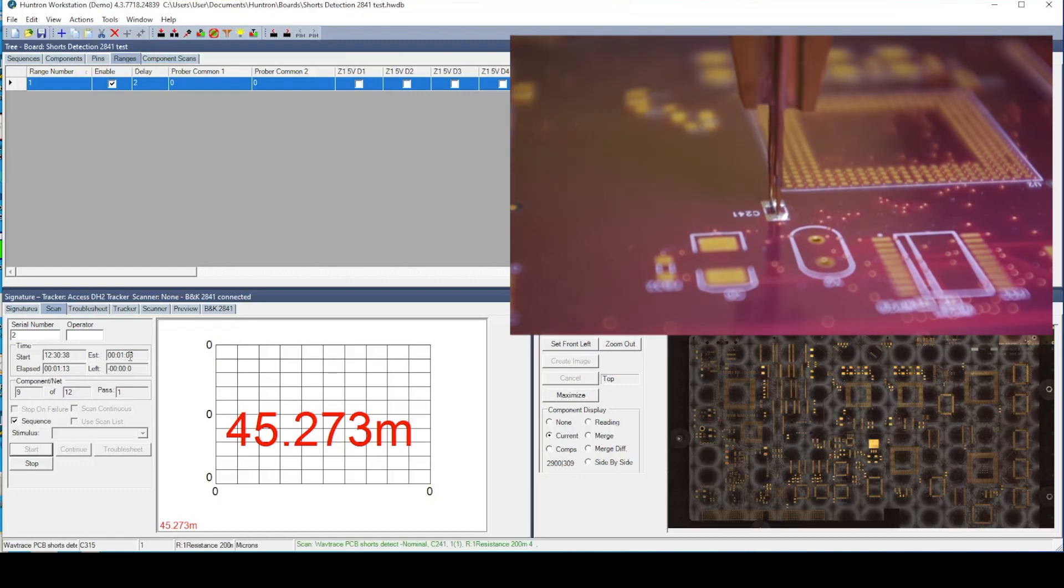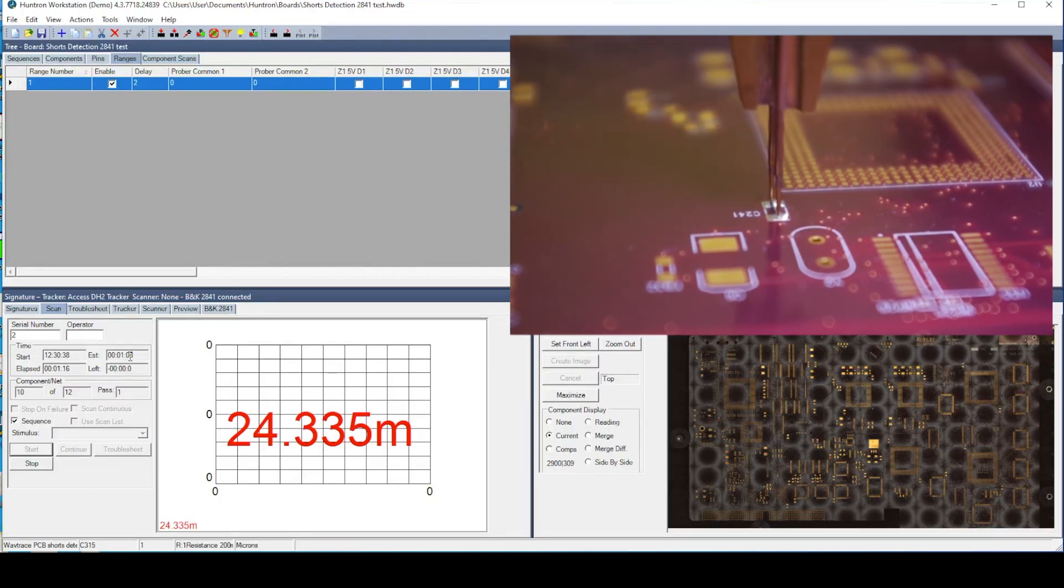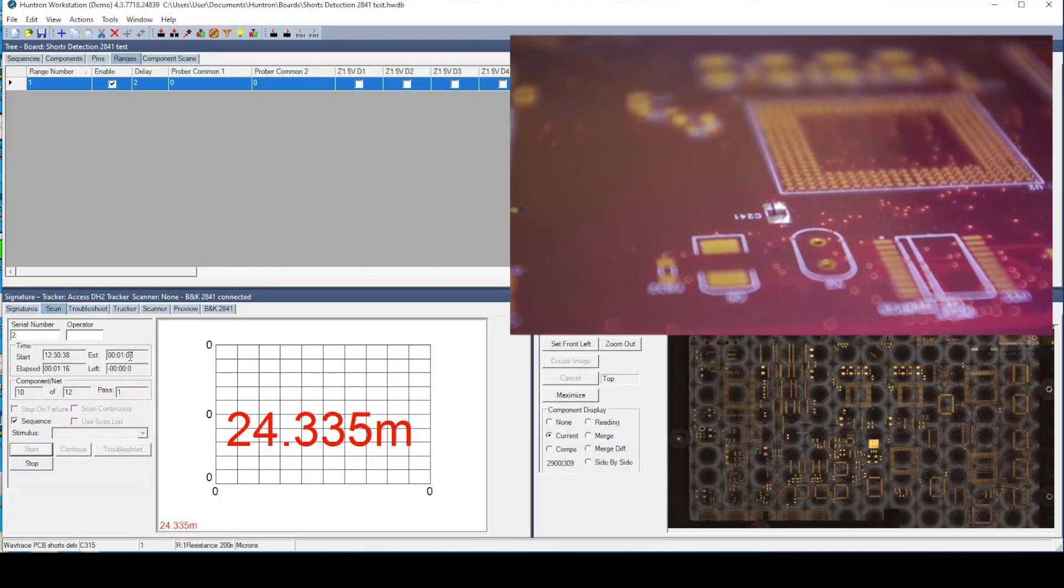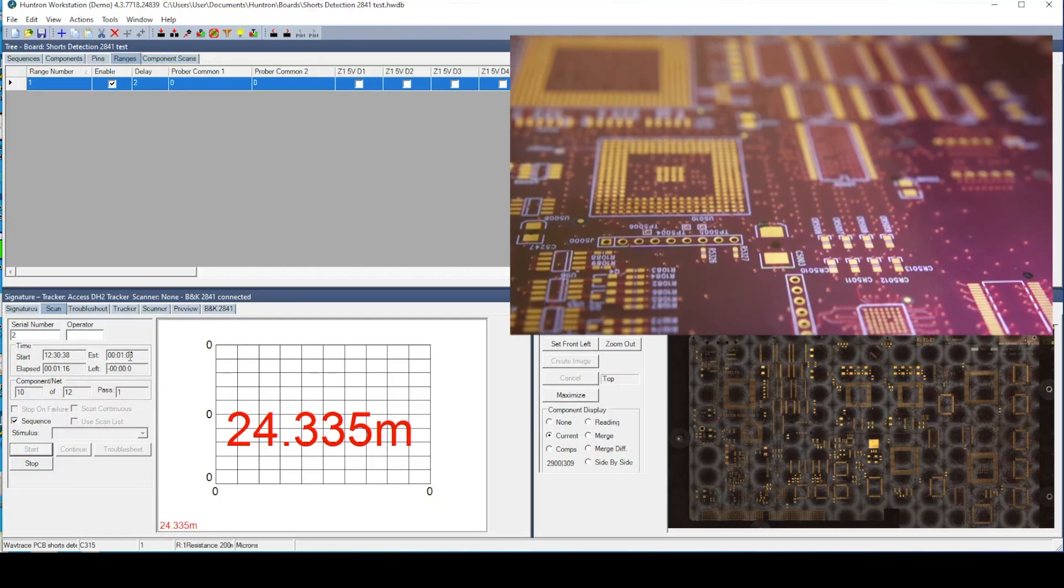When we get to the source of the short circuit, you will notice that the measurement is significantly lower than the others at 24 milli-ohms.